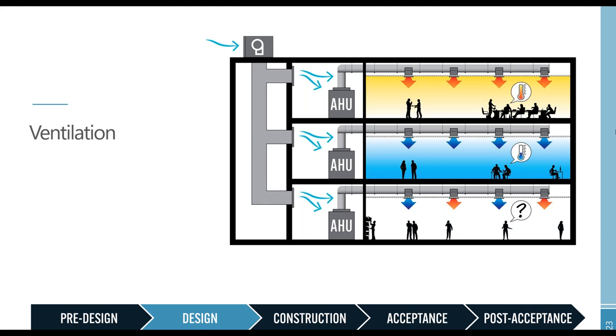And what followed was a series of back and forth conversations with the design team. At one point, the system was actually installed and turned over for operation. It took less than a week. Then a hot summer day came along and the air in the building was nice and thick and warm. Lots of occupant complaints. There were obvious signs of thermal comfort and humidity issues. At this point, they had to shut the system down or dial it back, way back.